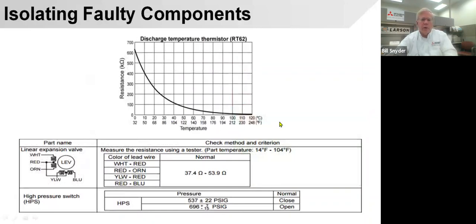Here's a thermistor chart. There are different thermistor charts, so make sure you get the right one. This one happens to be for an RT62, and it's telling me this is resistance. So at 400K ohms, I should be seeing 50 degrees. So if it was 50 degrees outside, I should be at 400K. At 100K, I should be somewhere between 104 and 122 degrees. So you can check out the thermistors and see if they're working.